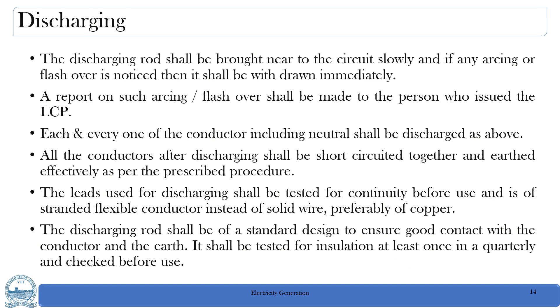The leads used for discharging shall be tested for continuity before use, and shall be of stranded flexible conductor instead of a solid wire, preferably made of copper. The discharging rod shall be of a standard design to ensure good contact with the conductor and the earth, and it shall be tested for insulation at least once quarterly and checked before every use. Earthing shall be done on all sides of the place of work, that is both the ingoing and outgoing side. Short circuiting shall not be treated as a substitute for earthing, and standard earthing rods must be used. The earthing and discharging shall be done only by an authorized person.